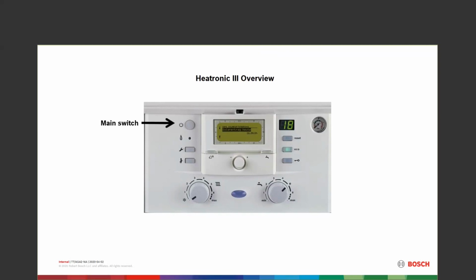And the main switch is that round knob on there, that push button switch. Next thing that happens is once it's fired up, you're going to see that little LED for the burner light up. It's going to tell me that the burner's on. Next one we got is our service key or service function keys, wrench button, whatever we like to call it. Wrench button gets us in and out of service functions. We've got this burner test key of the service guy, the man with the ladder, the man with the hat. He gets us in and out of each service function as well as going into a forced combustion. So he does a bunch of different jobs.